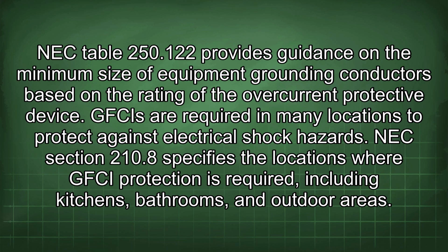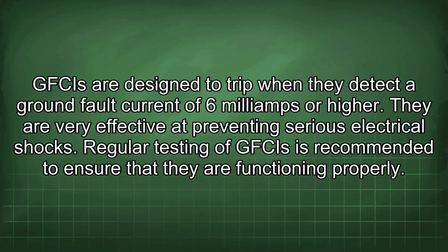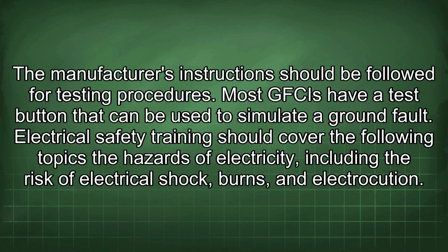GFCIs are required in many locations to protect against electrical shock hazards. NEC Section 210.8 specifies the locations where GFCI protection is required, including kitchens, bathrooms, and outdoor areas. GFCIs are designed to trip when they detect a ground fault current of 6 mA or higher. They are very effective at preventing serious electrical shocks. Regular testing of GFCIs is recommended to ensure that they are functioning properly. The manufacturer's instructions should be followed for testing procedures. Most GFCIs have a test button that can be used to simulate a ground fault.